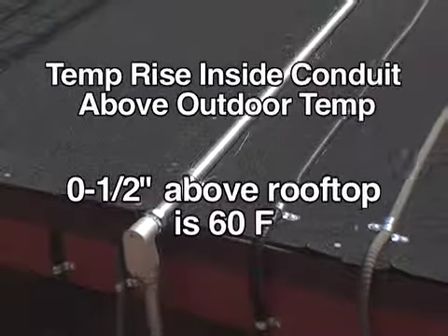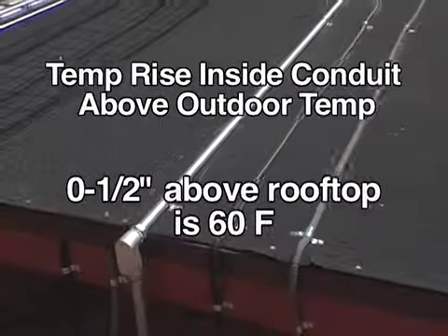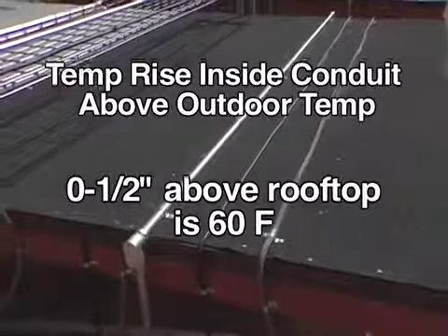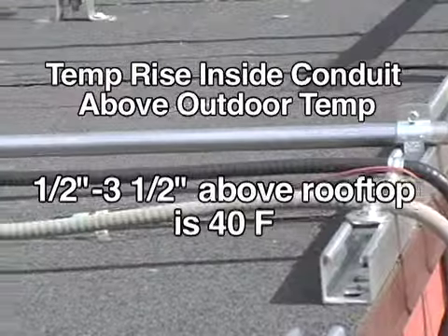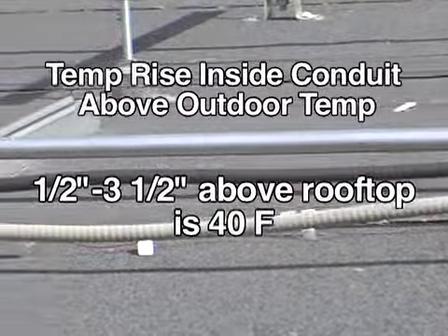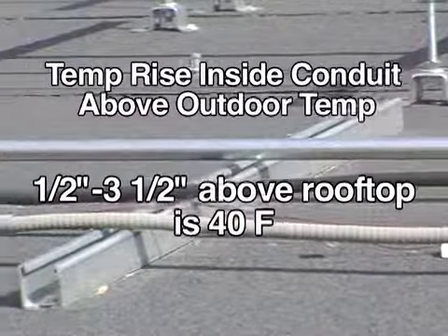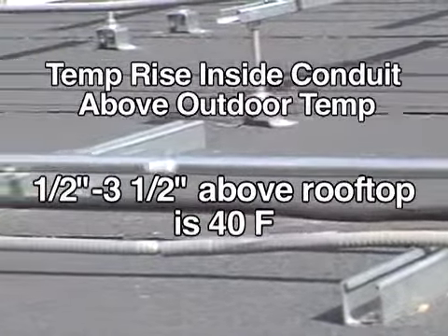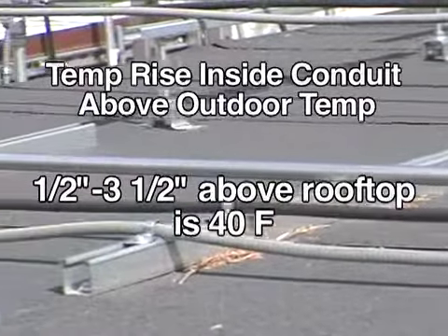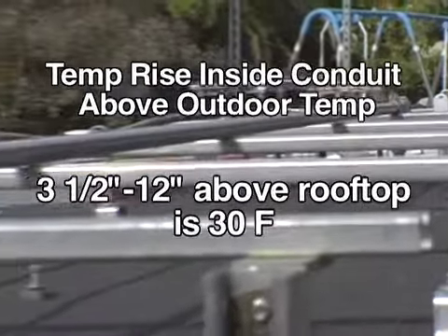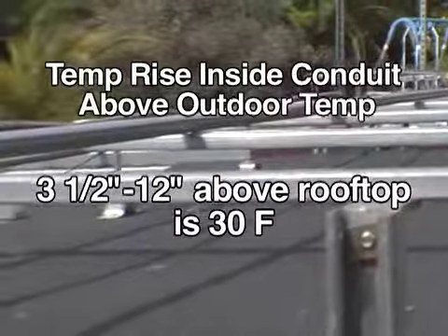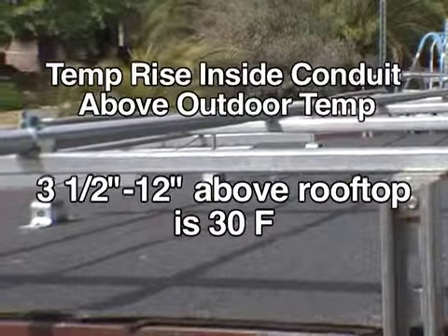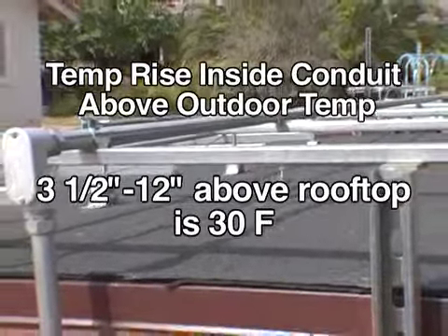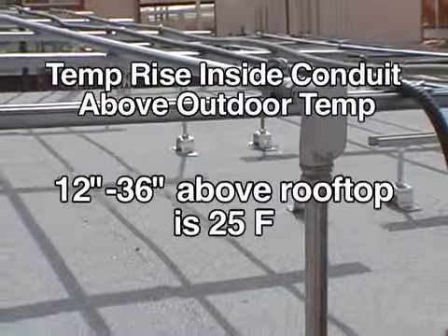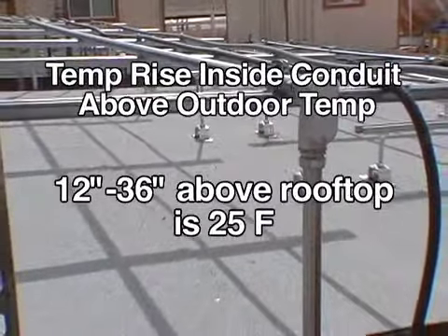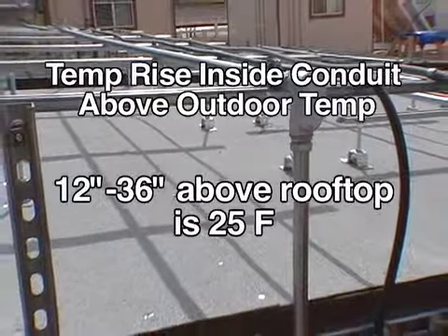The temperature rise inside the conduit for 0 to ½ inch above the roof is 60 degrees Fahrenheit above the outdoor temperature. The temperature rise inside the conduit for ½ inch to 3½ inches above the rooftop is 40 degrees Fahrenheit above the outdoor temperature. The temperature rise inside the conduit for 3½ inches to 12 inches above the rooftop is 30 degrees Fahrenheit above the outdoor temperature. And the temperature rise inside the conduit for 12 to 36 inches above the rooftop is 25 degrees Fahrenheit above the outdoor temperature.